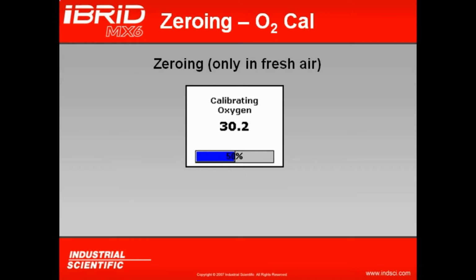The next thing the instrument will do is calibrate the oxygen sensor to the room air. We want to ensure that whenever the instrument is zeroing, we zero only in fresh air, because the O2 calibration is going to be based on purely the ambient atmospheric conditions. So if your oxygen concentration is anything other than 20.9, it may skew your oxygen calibration.